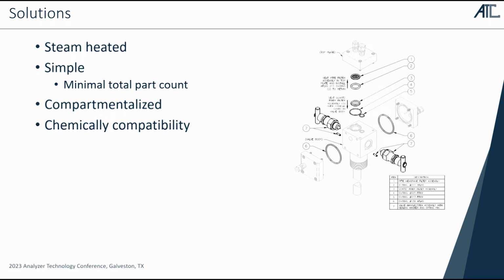Well, how are we going to address that? For starters, we want to ensure it doesn't foul. In this case, we want to ensure that the probe is heated in such a way that the sample will remain heated, and we won't get the formation of solids and salts that we're talking about. The next thing is we want to ensure that this is easily maintainable, right?